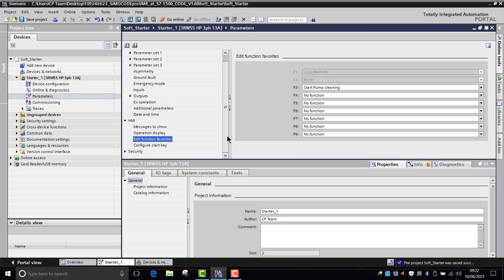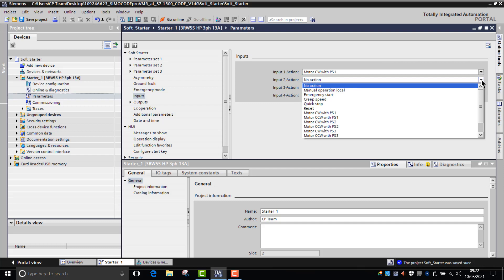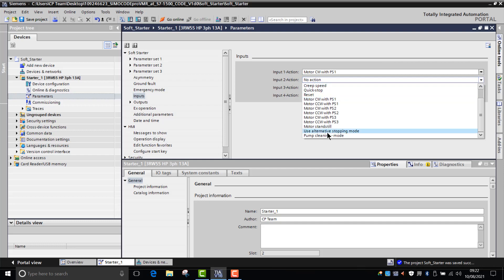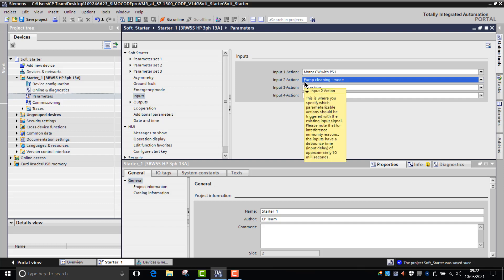Another way of accessing the pump cleaning feature would be through the inputs. On the soft starter you have four inputs which are built into the unit. You can switch one of those inputs and have it as being the pump cleaning function. So if you initiated input two on the soft starter, it would then enter the pump cleaning mode.